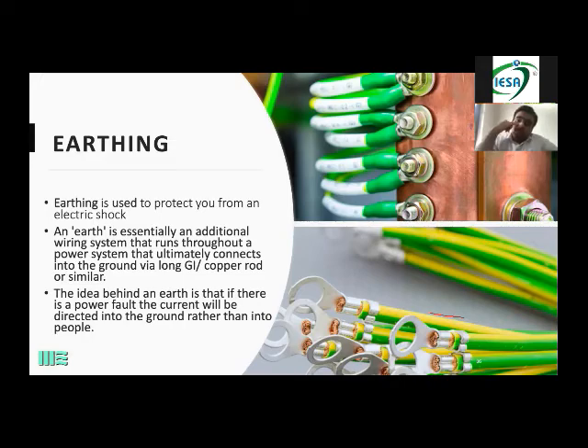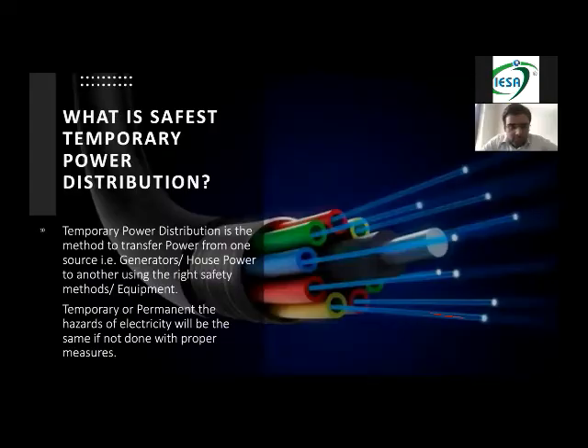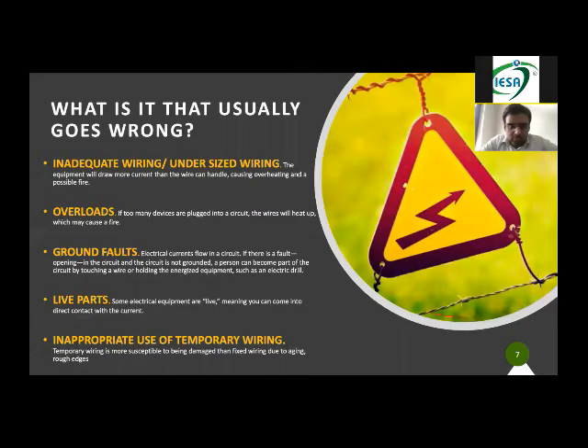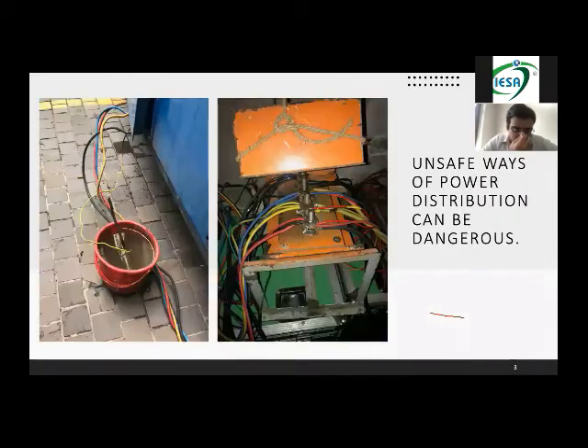So what is that earth? I'll just go back again, sorry, to my first slide because it will be easy for you to understand. I'll just open my pointer here. Okay. If you see, there is this black wire, these wires could be coming from the genset, this black, yellow, blue and red. You see this bucket earth. Again, first of all, when we are saying earthing, the name itself says that earthing requires earth. This can't work at all. It is just a formality.